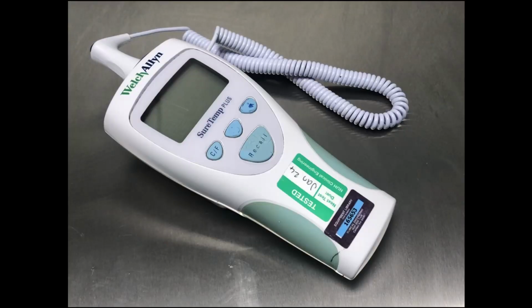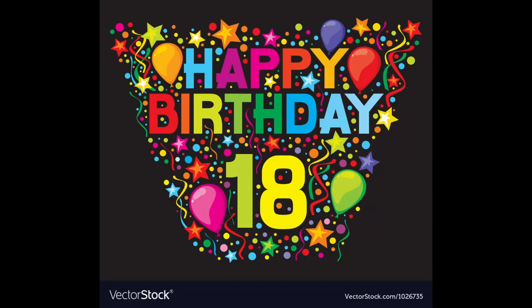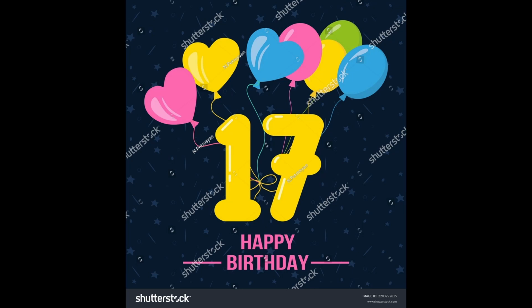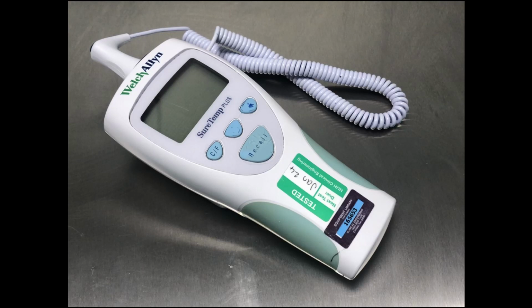So returning to our mode selection and our patient groups, adult is 18 years and older, pediatric is 17 years and younger, not sure what you do for people in between those ages, and for axillary readings in those age 17 years and younger, you must always use pediatric mode. Normal mode, adult, is the default operating mode for temperature measurements.